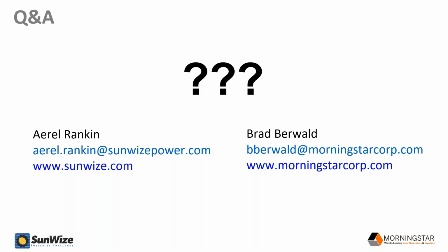Sure. There's two things to think about here. One is, what is the actual certification or listing? In this case, we're talking Class 1 Division 2. A more standard safety version might be UL 1741, the famous one used in the solar industry. That standard is defined by a panel in conjunction with a lab, with lots of contribution from the industry. Once that's defined, the testing and listing requirements are all part and parcel with getting that listing, and it has to be tested to that standard.